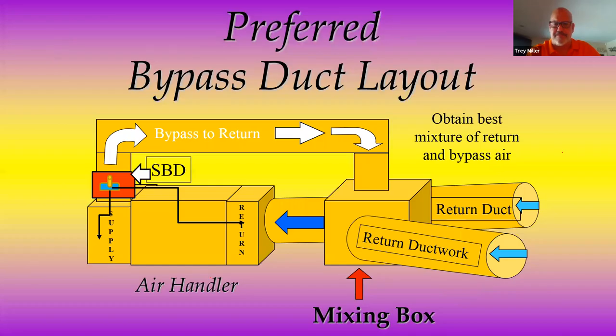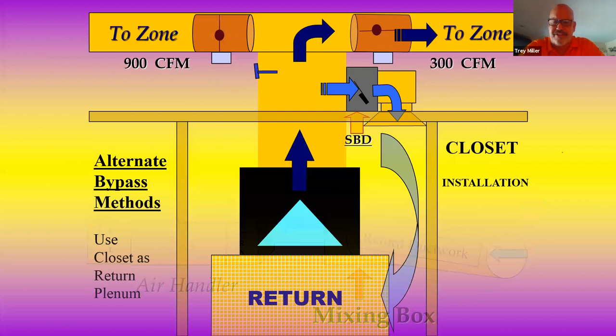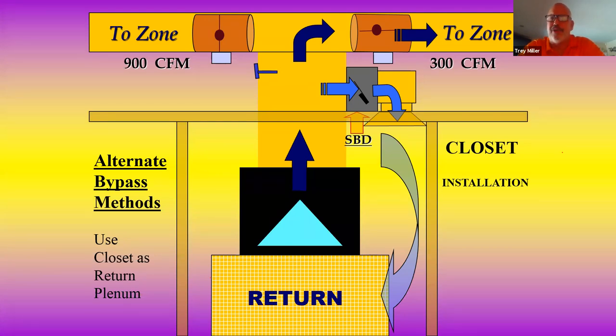But the mixing box mixes the air and pulls it through mixed. We're creating the turbulence. But you don't always have this much room, so you do have a bypass. And this is in the closet application, sitting on a platform. If you're sitting on a platform pulling return air through a louvered door, guys, this is beautiful. I've got hundreds of these working in the Georgia market, working without any problem. And the beauty of it is, guess what? I just eliminated the number one problem you have with closet applications, sweat on the air handler.